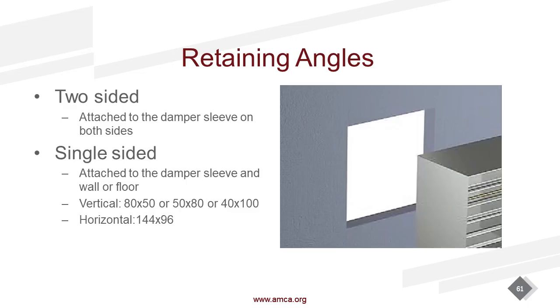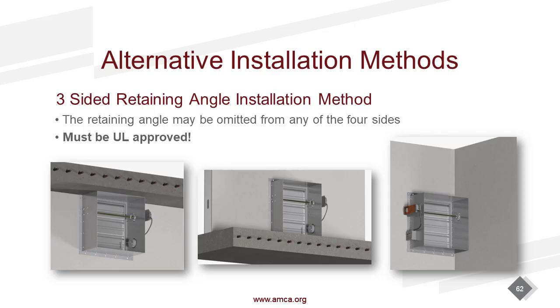There's a spacing requirement of that fastener. It usually reads, first fastener starts 2 inches from the end, minimum of 2 fasteners, and a fastener every X number of inches. Well, when you buy an angle from a damper manufacturer, we have the ability to pre-punch those holes, make it nice and neat for the installing contractor. No thought. Angles could be made in the field, then the contractor has to measure and put those fasteners where they need to go. I don't know of any building inspectors that carry rulers with them, but a lot of them will actually look at that. So that's something to keep an eye on for my installers.